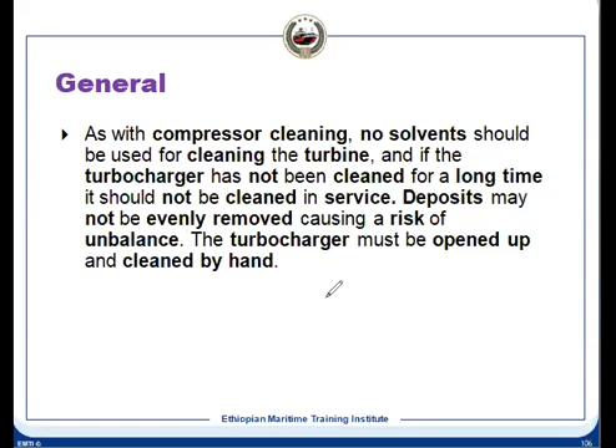So the air cooler also has to have some maintenance. What is the maintenance we do? On the air side, it gets deposits of oil and the particles which the air is carrying. Suppose the turbocharger air filter is not in good condition, then more deposit will be there. If it is in good condition, less deposit will be there. Because you cannot remove 100%, deposits form on the air side, because the fins or passages are very small, and it is an extended fin area heat exchanger. The fouling rate is higher because the passages on the air side are very small. So that has to be cleaned. It means the air side has to be cleaned as well as the cooling water side.